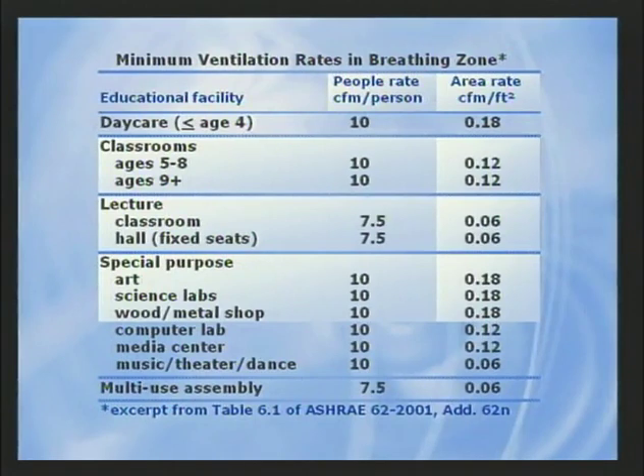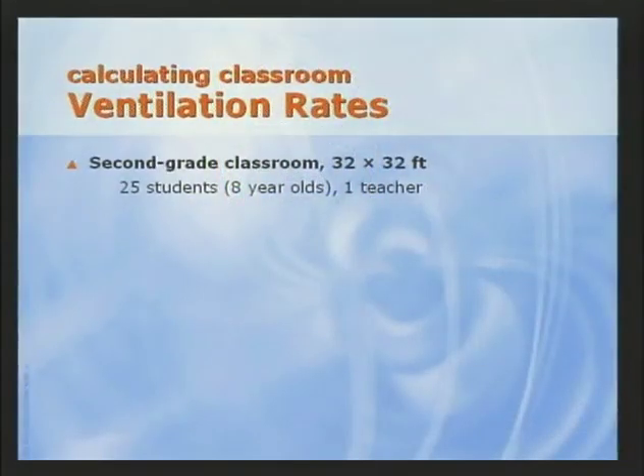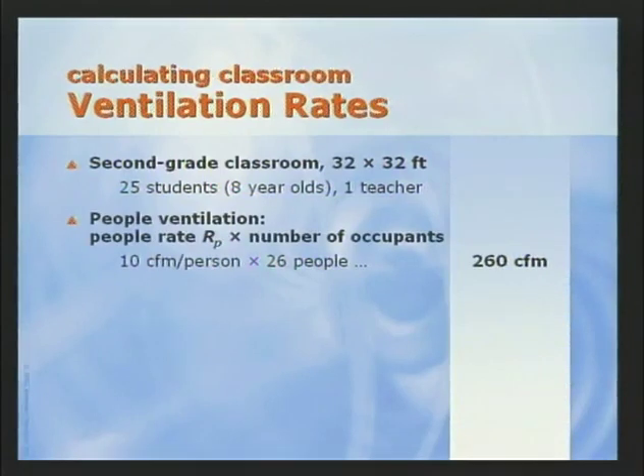Note that the area factor, 0.12 CFM per square foot for classrooms, is double that required for lecture halls, while the value for daycare and art rooms goes up to 0.18 CFM per square foot. These values reflect the contaminant load expected to be generated in these building areas, regardless of the people. Using the new procedure, let's quickly calculate the ventilation rate for a second grade classroom, measuring 32 by 32 feet that will be occupied by 26 people. The people-related ventilation rate for 8-year-olds, determined using the 10 CFM per person from Table 6.1, and the predicted number of people in the room, in this case 26, is 260 CFM.